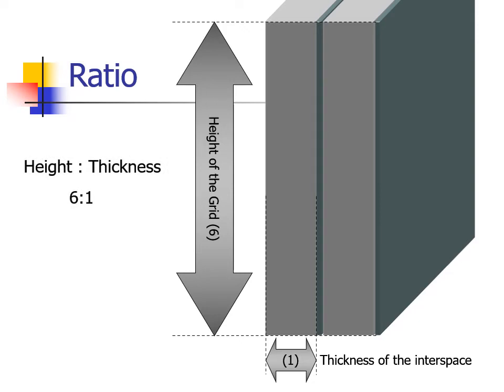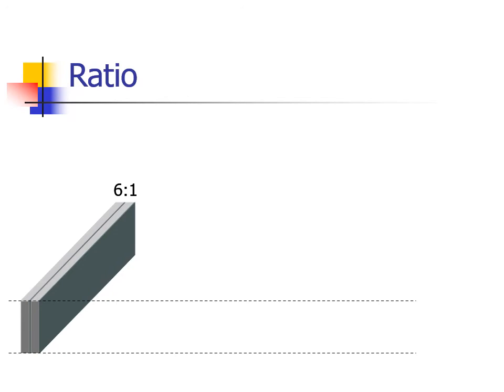Grid ratio is commonly expressed in units of height compared to interspace thickness, and the interspace thickness is always expressed as one. So, a six-to-one grid will always be six times higher than the thickness of the interspace material. Here we have an example of a six-to-one grid. Let's draw some guidelines tangent to the top and bottom of our six-to-one grid.